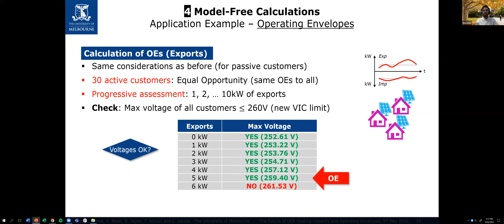We make the checks, voltages are okay, and we can see our results. Our 30 active customers could export up to 5 kilowatts without creating voltage issues in our low voltage network, whereas at 6 kilowatts of export for all 30 customers, voltages go beyond statutory limits. So the operating envelope for this particular case will be 5 kilowatts.